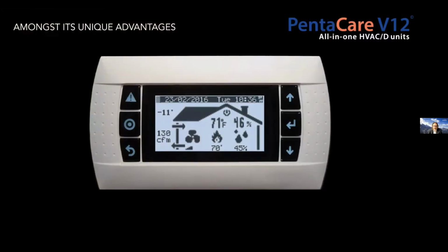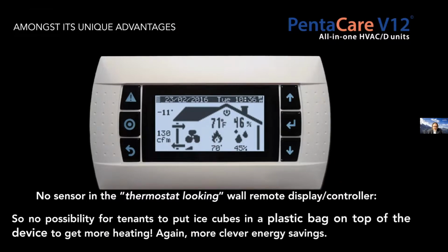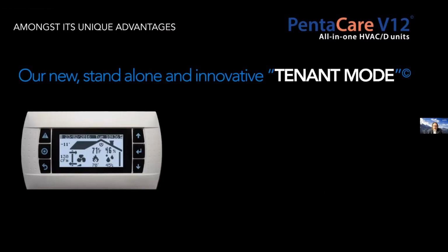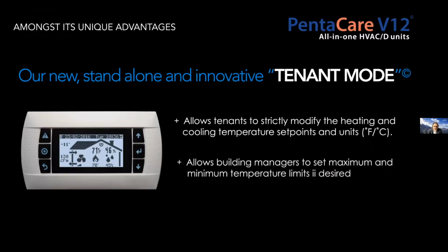So, a few advantages. This is a thermostat-looking device to control a unit. There's no sensor, meaning no possibility for tenants to put ice cubes in plastic bags on top of the device to get more heating. Also, we have a tenant mode making sure that tenants are allowed only to change the heating and cooling temperature set points if needed, and allowing building managers to set maximum and minimum temperature limits if desired.